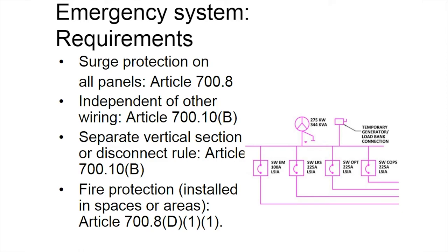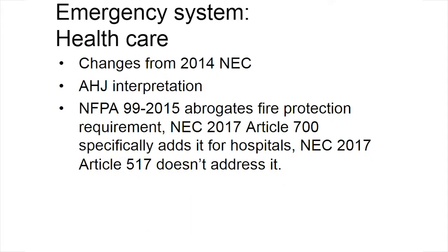And here's an erratum. The slide references 700.8 for the fire protection requirement, but that requirement actually appears in 700.10. The requirement has evolved considerably over the last several editions of the NEC. In 2002, it covered specific occupancies, and one of the ways to comply was just to have a fully sprinkled building. Over time, the requirement changed from being in a fully sprinkled building to being in a space or area that's protected by a fire suppression system.